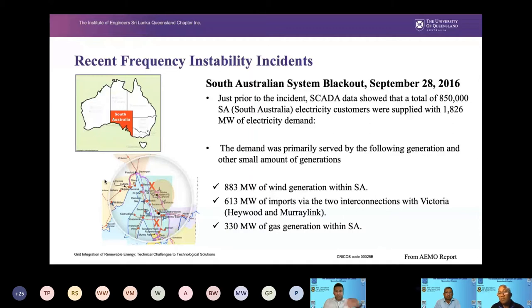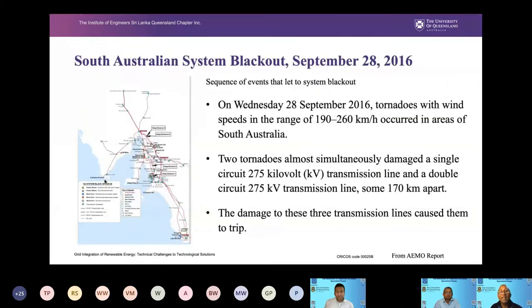And then about 600 megawatts was supplied by two interconnections. Those of you who know this, South Australia is interconnected with Victoria through two interconnections. One is the Heywood interconnection, the other one is Murraylink. Heywood is an AC connection. Murraylink is a DC connection, a fixed 200 megawatt connection. And in addition to those two, there was 330 megawatts of gas generation as well. Let's see what happened on the day leading to this blackout event.